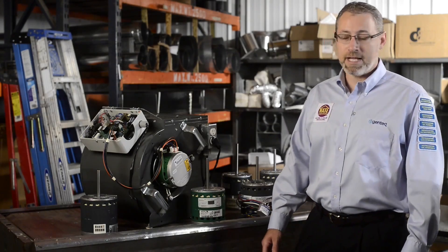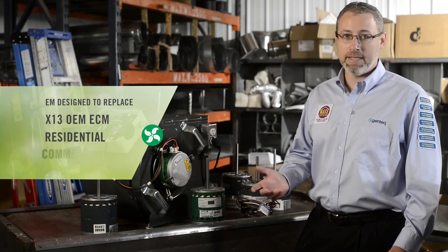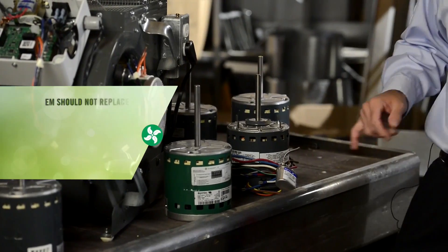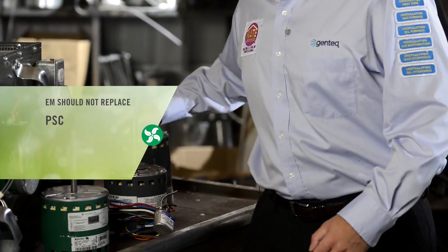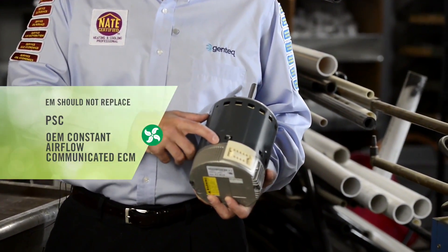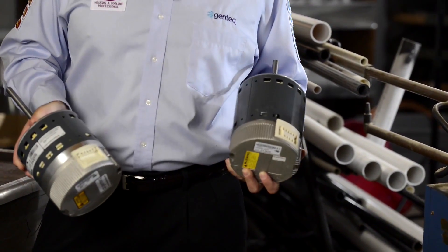The Evergreen EM was designed to replace the X13 OEM ECM indoor blower motor, which is primarily used in residential and light commercial applications. It can also replace similar competitor's models. The Evergreen EM should not be used to replace PSC indoor blower motors — that's motors with run capacitors. It should also not be used to replace the OEM constant airflow communicated ECM indoor blower motors, such as our model 3.0 with the 4-pin communication connection, or the model EON with the 16-pin communication connection.